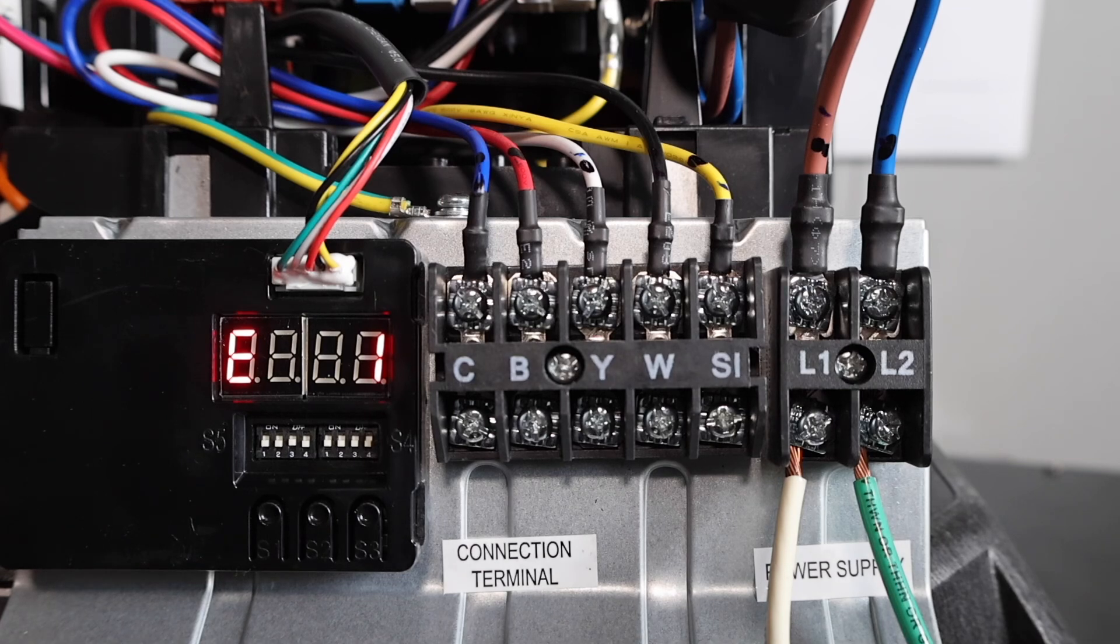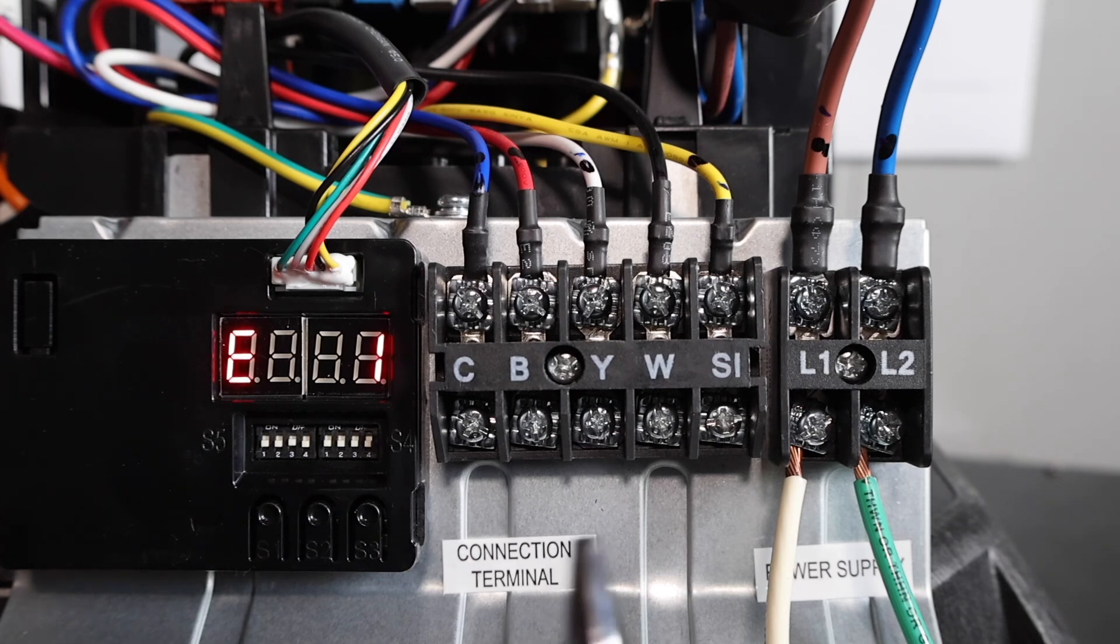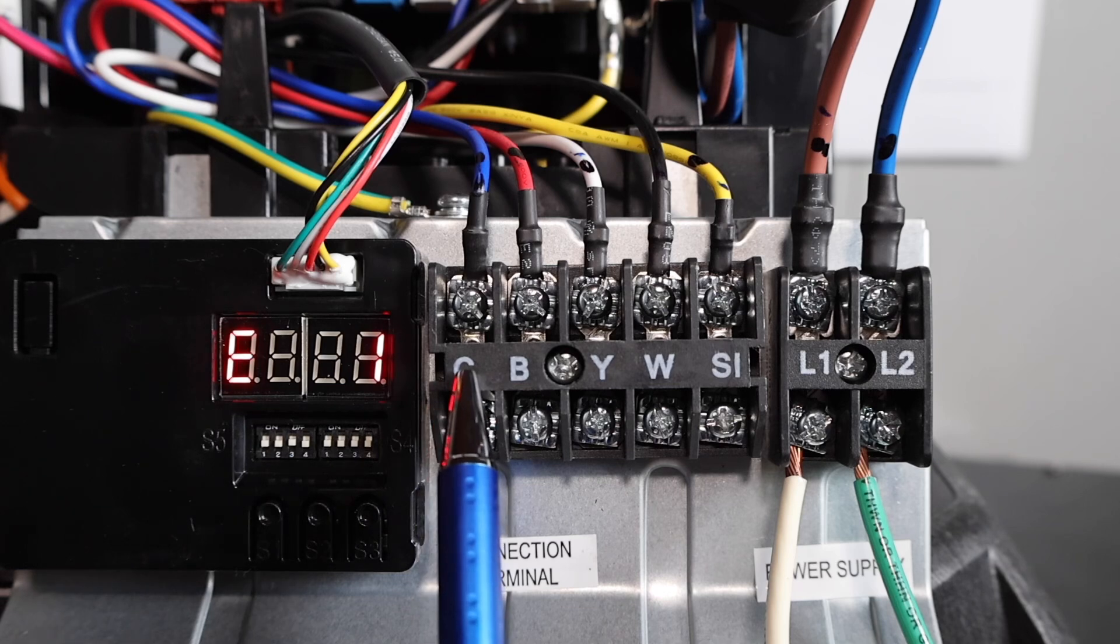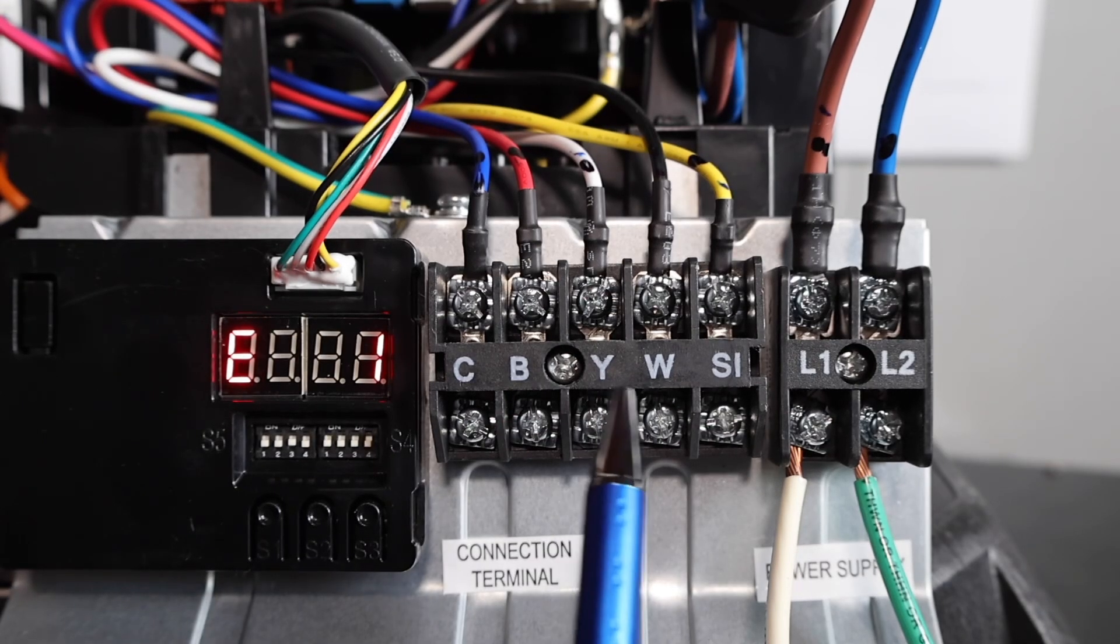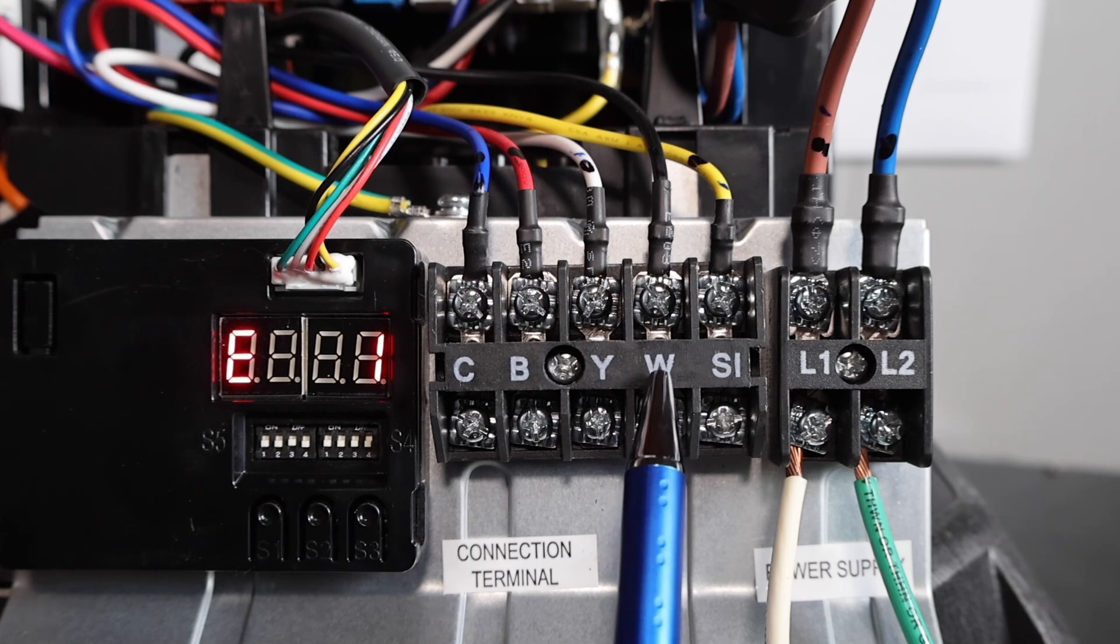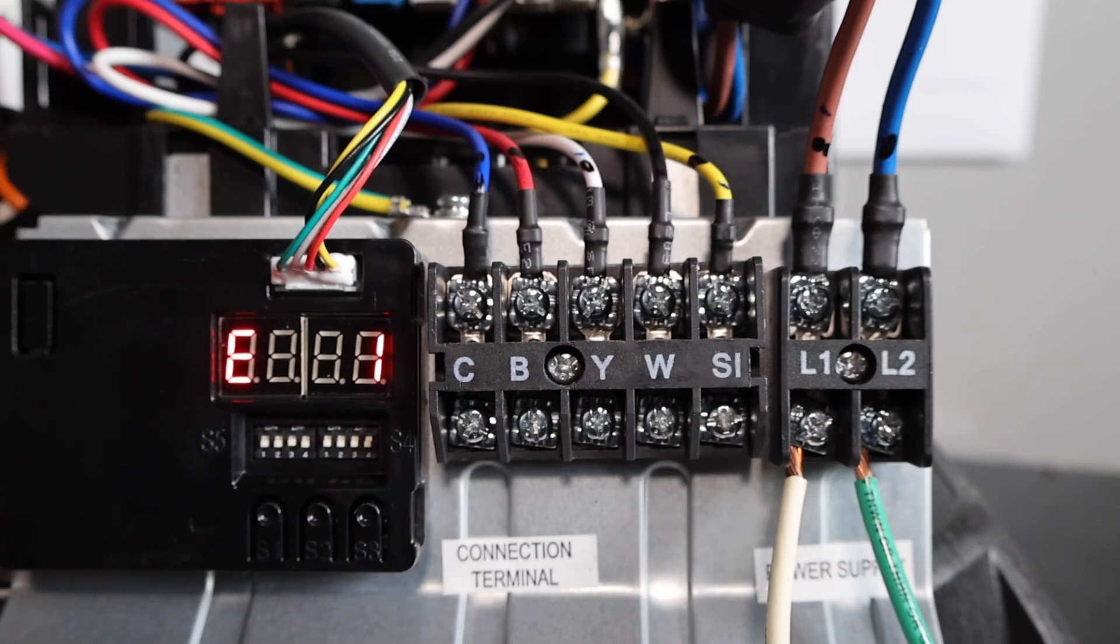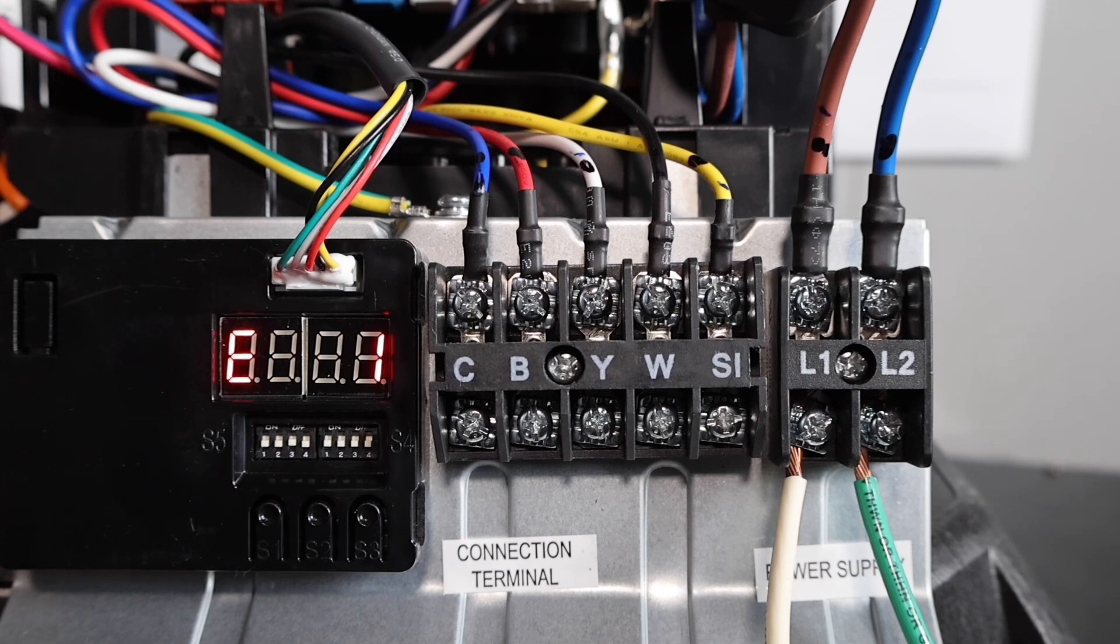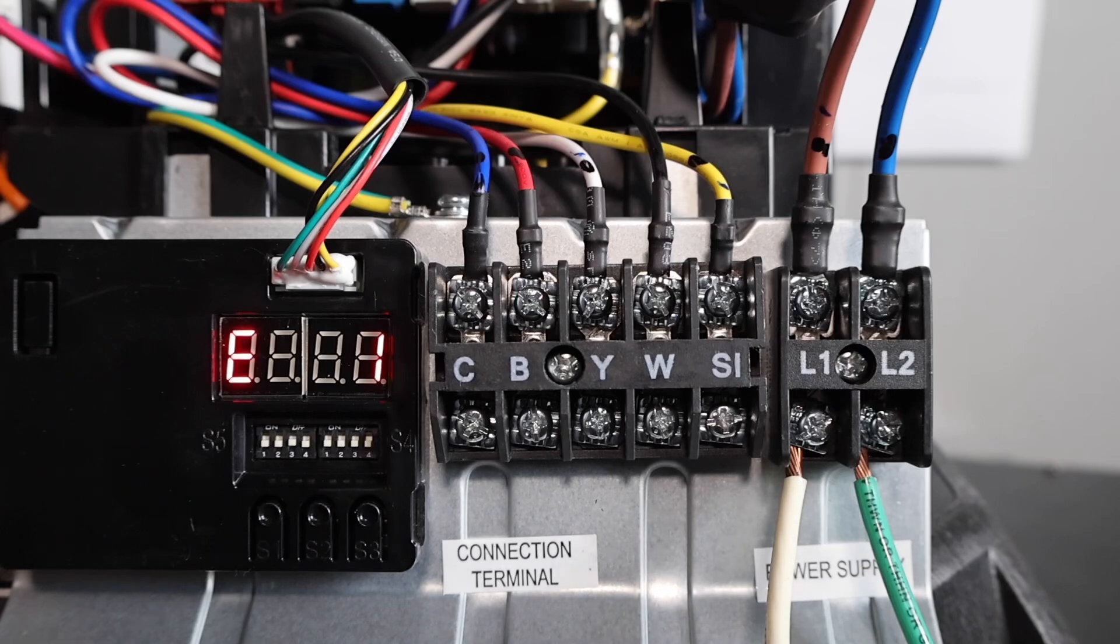The main reason we're here today is going over the low voltage and what terminals are on this outdoor unit. You have a five terminal strip for your low voltage: C for common, B for your reversing valve because we energize in heat on this unit, Y for your compressor call, W will bring on your backup heat during defrost - you do not want to hook this up in a gas heat application, only during electric heat. And then the SI terminal is Friedrich's proprietary terminal, a communicating terminal between indoor unit and outdoor unit if you have the matching Friedrich air handler. If you don't have that air handler, you're not going to hook that SI terminal up. And obviously off to the right we have our high voltage terminal L1 and L2, 240 volts in.